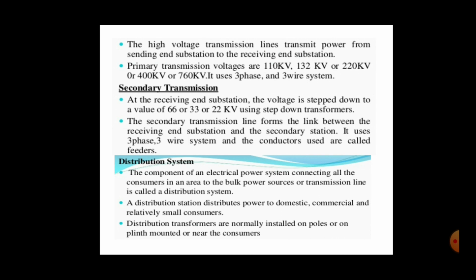Next, secondary transmission. At the receiving end substation, the voltage is stepped down to a value of 66 or 33 or 22 kV using step down transformers. The secondary transmission line forms the link between the receiving end substation and the secondary substation. It uses a three-phase three-wire system, and the conductors used are called feeders.